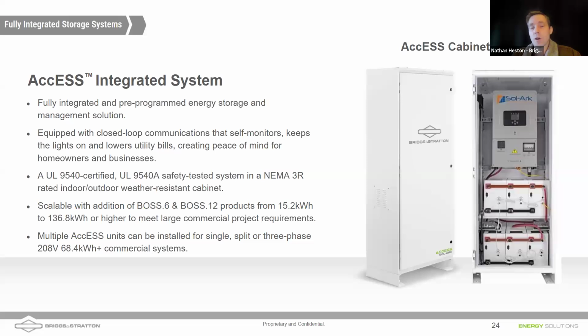One of the things I mentioned, if you have a larger wind system, is you do have to have a power dump. So you would need to have a load bank to take care of excess power if that wind gets too high and exceeds the ratings that the Sol-Ark can take in. So yes, there are some examples. We used to see a lot of wind. I remember reading my old Home Power magazines, and you would see micro hydro articles and wind power. But I think Nathan, you had mentioned with solar being 25 cents a watt, with no moving parts, no heat dumps, that it's really gone away a lot. But I'm excited to see some pictures or stories about people integrating them still.